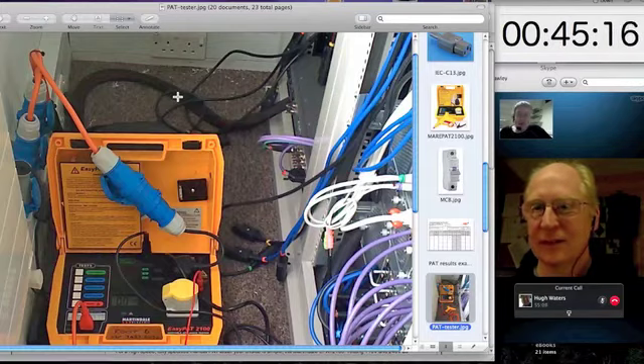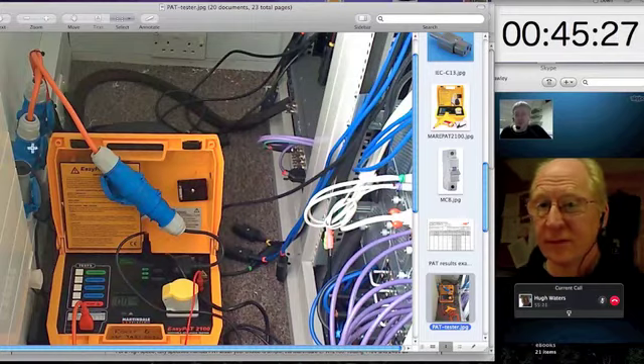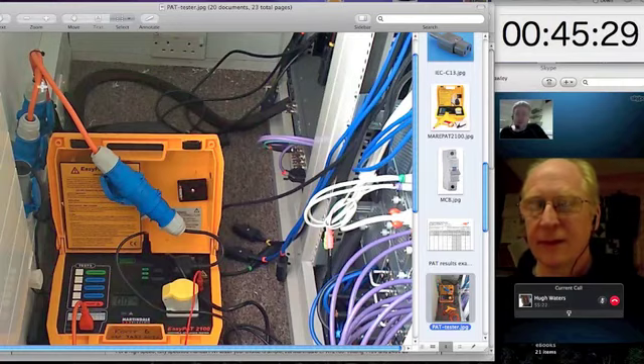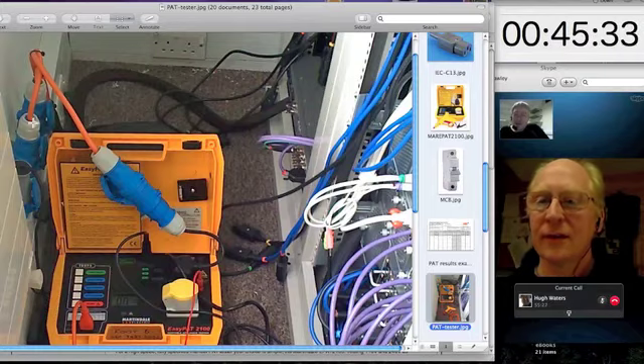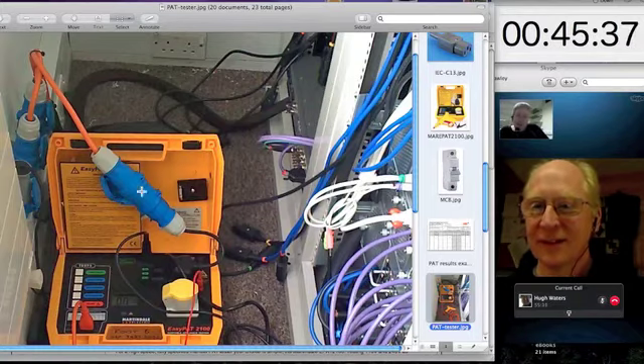If each one of your cabinets is fed by one or increasingly two C16 connectors, because you might have a split power supply in a big facility, you might have UPS backed power or generator backed power, and so one supply may be the generator backed power and one supply may be just the raw mains. Then no piece of equipment like a Hoover or a phone charger ever comes with a 16 amp CEEform connector on it. It just doesn't happen.